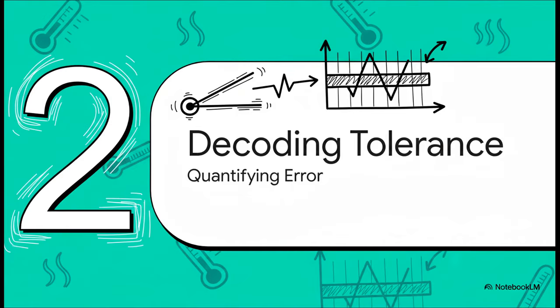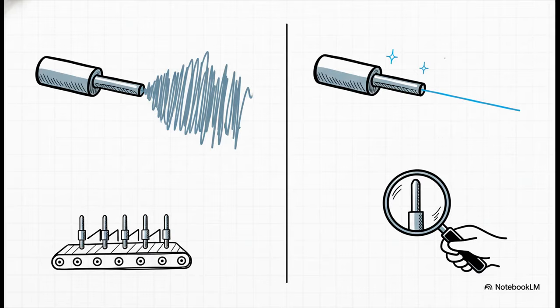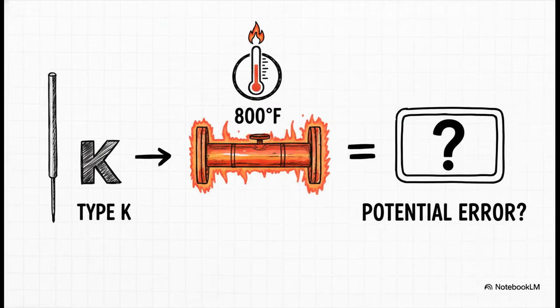Let's decode what tolerance really means, especially when we're talking about the workhorse of the industry, the thermocouple. Turns out, not all new thermocouples are created equal. Far from it. They're actually sorted into two different grades. You've got your basic, standard limits of error grade, and then you have a premium version called special limits of error, which are manufactured to be much, much more accurate from the get-go. To really see what this means, let's do a quick and dirty calculation. We'll take a super common sensor, a standard type K thermocouple, and see what its potential error looks like when it's trying to measure something that's 800 degrees Fahrenheit.